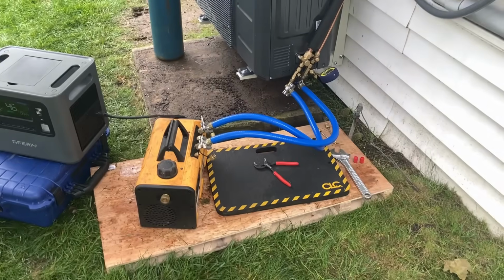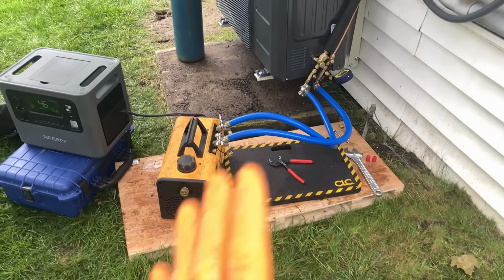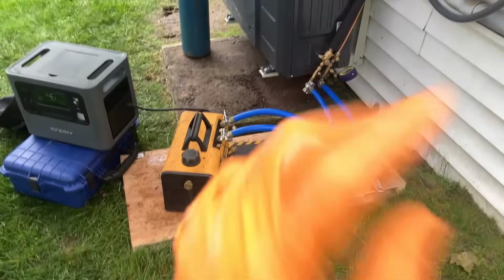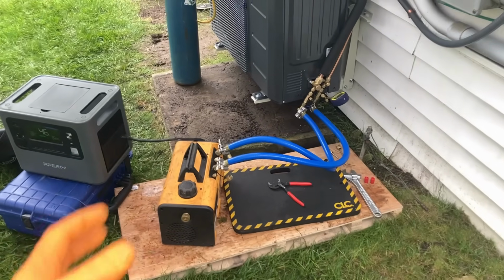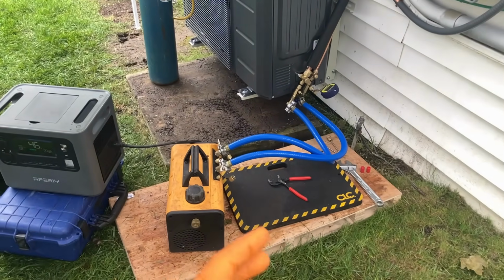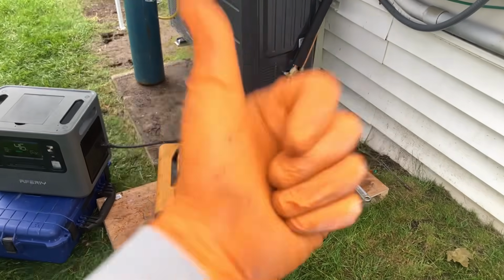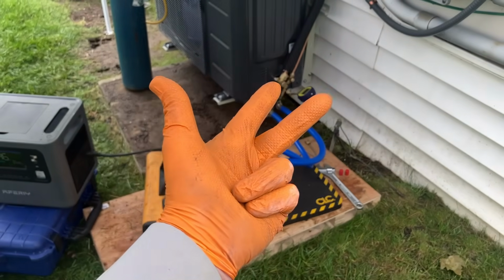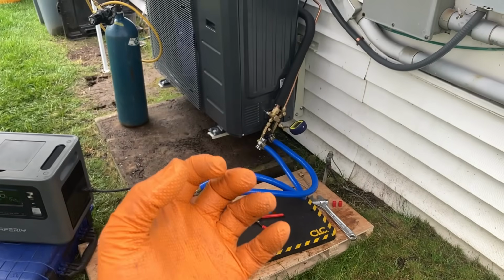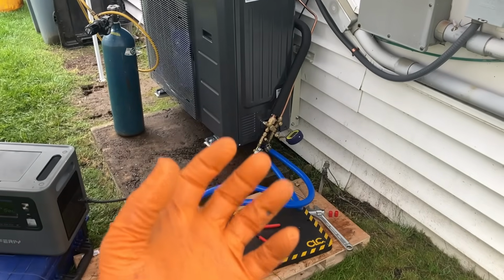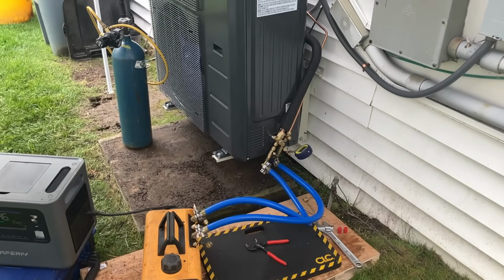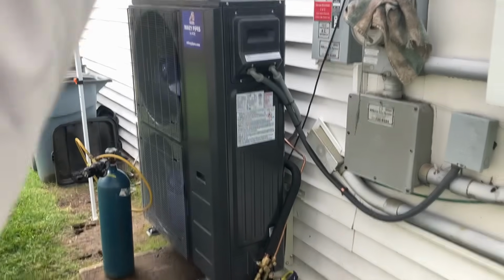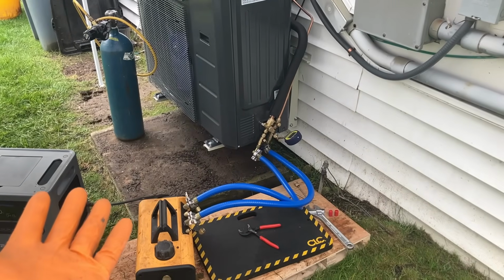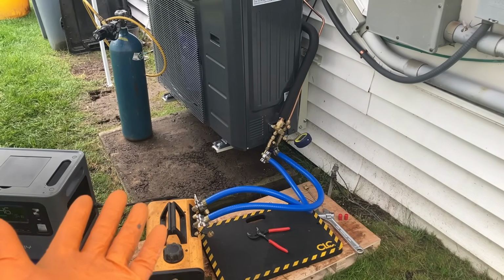12:35, all right, let me explain to you who don't know what's going on. Right now we are vacuuming down the system. We're essentially vacuuming down the evaporator coil, the suction, and the liquid line. We're removing all of the atmosphere, all the non-condensables, but most importantly, moisture. You know there's moisture in those lines, it's been open to the atmosphere for a few hours during the installation process, right?